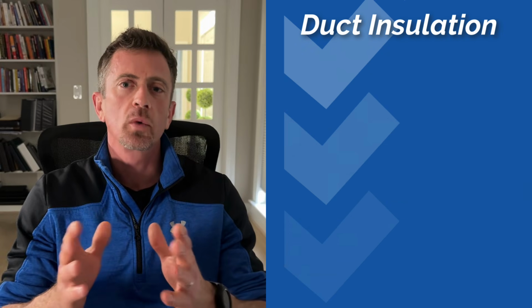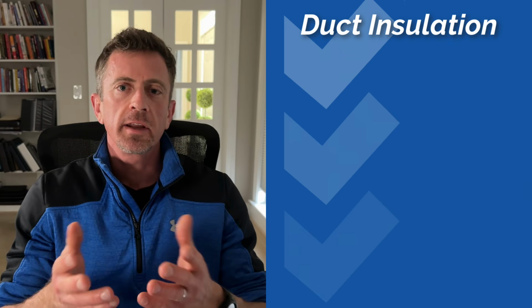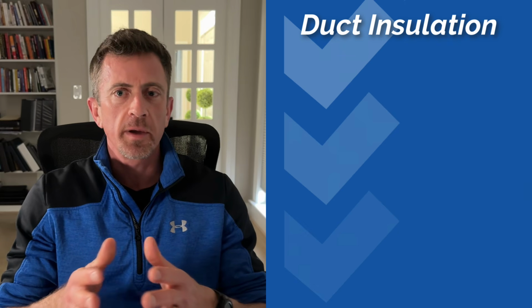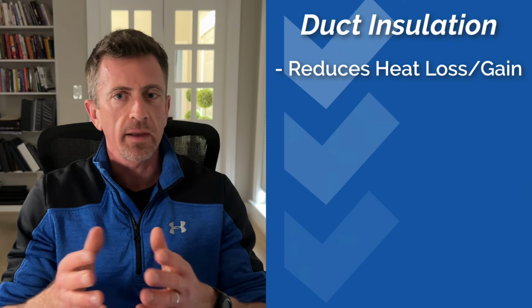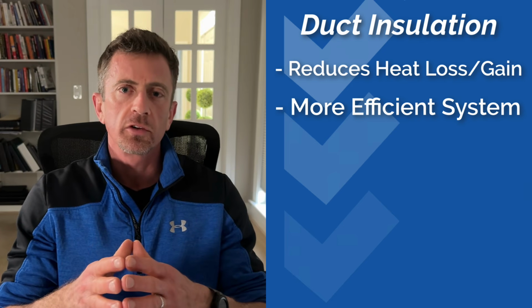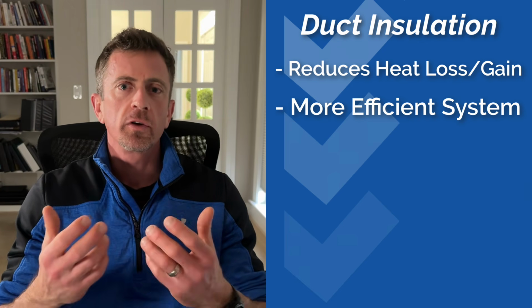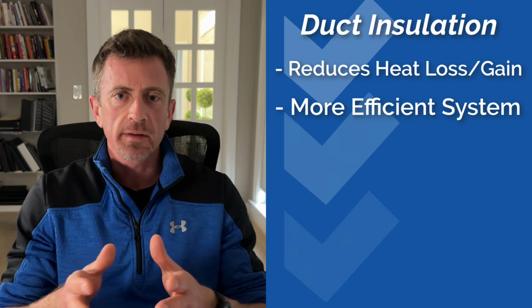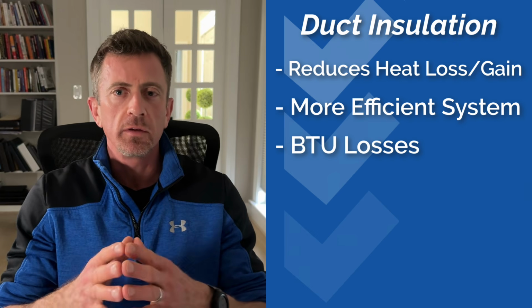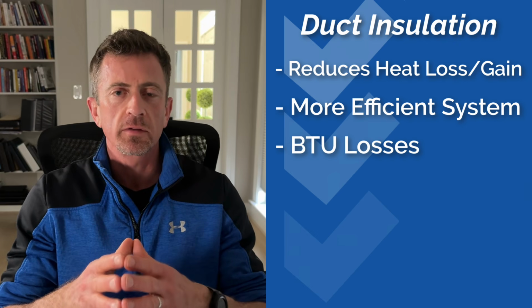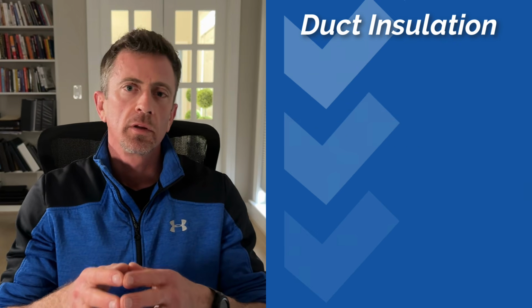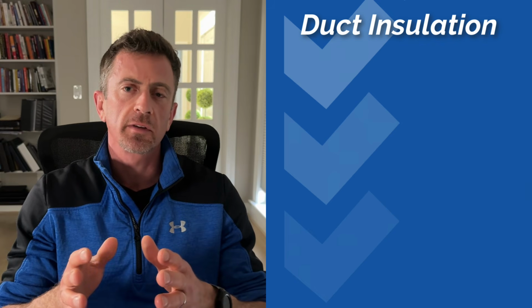Now let's discuss ductwork insulation. Insulating ductwork, especially in attics or crawl spaces, reduces heat loss or gain, and it makes your system a lot more efficient overall. Remember, if your ducts are leaking or poorly insulated, you're losing those valuable BTUs before they even reach the rooms they're meant to serve. There's a few different types of insulation that we're going to discuss.